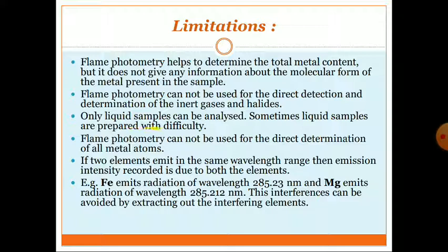Only liquid samples can be analyzed. Sometimes liquid samples are prepared with difficulty. Other solid or gaseous samples cannot be analyzed with the help of this flame photometer. Then, flame photometry cannot be used for the direct determination of all metals. Second last, if two elements emit in the same wavelength range, then the emission intensity recorded is due to both the elements. We will see an example of that.